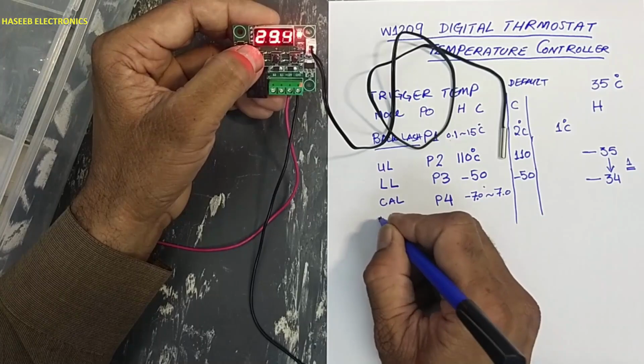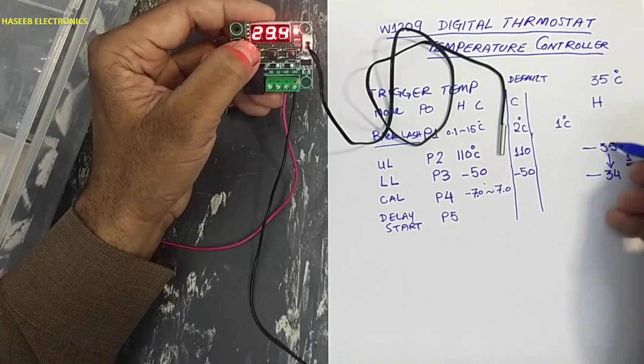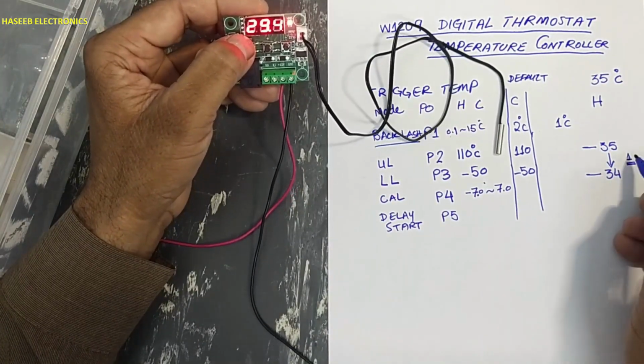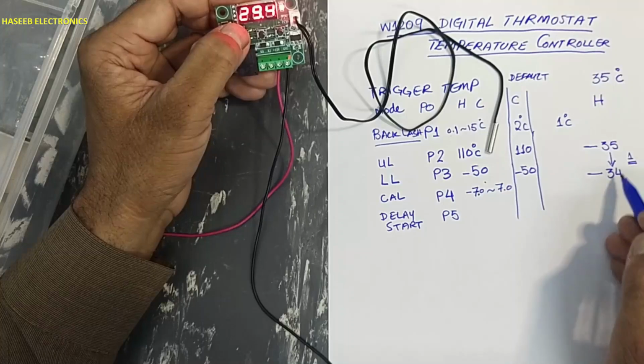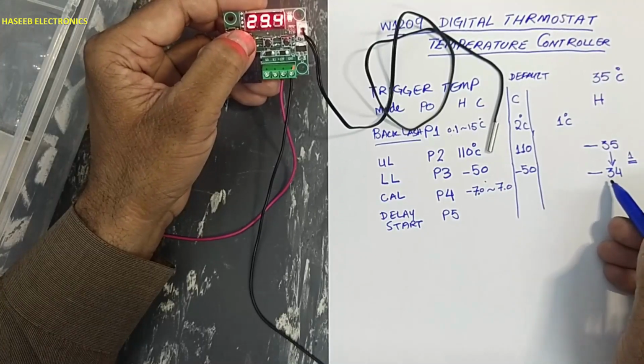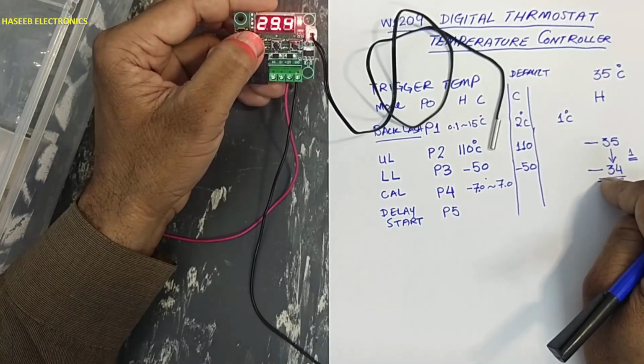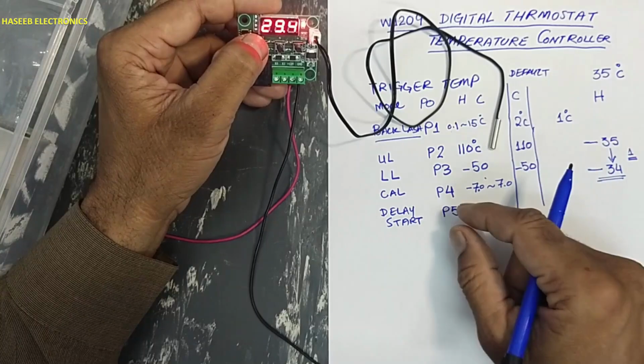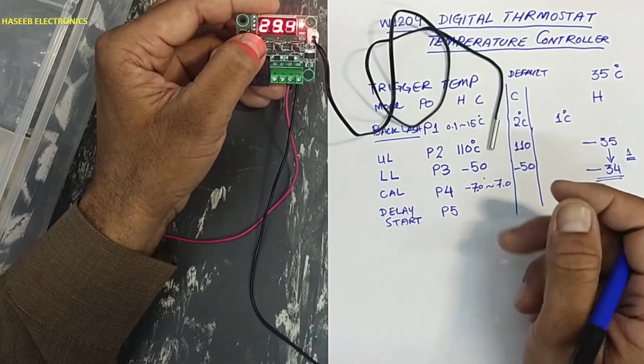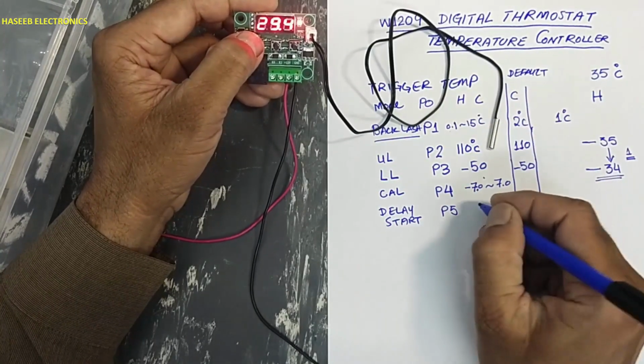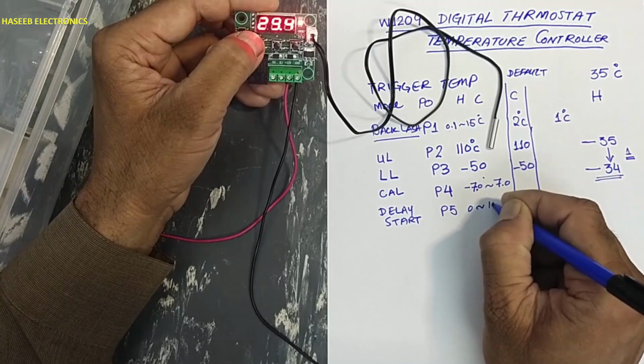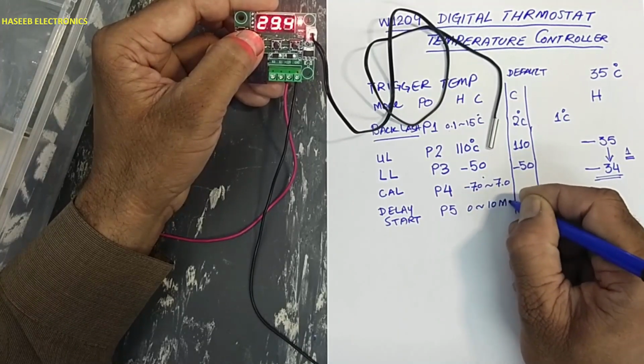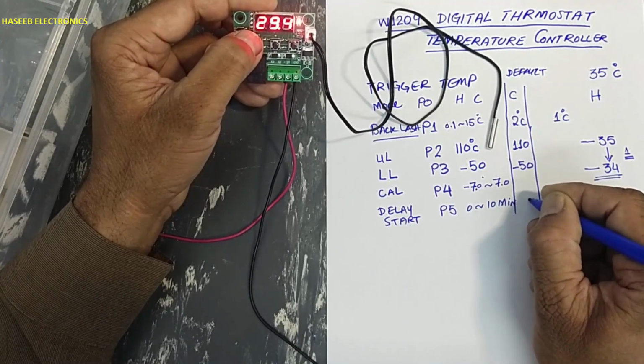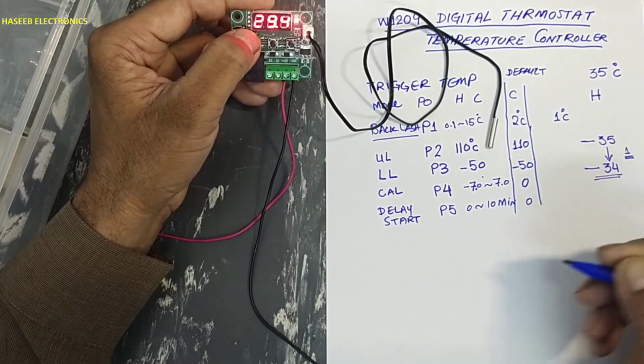That option is for delay start. When upper limit minus backlash, 34 degrees, when this condition will meet, how much time we will allow to delay to turn on the heater? That is from 0 to 10 minutes. The default setting is 0. Here is default setting 0.